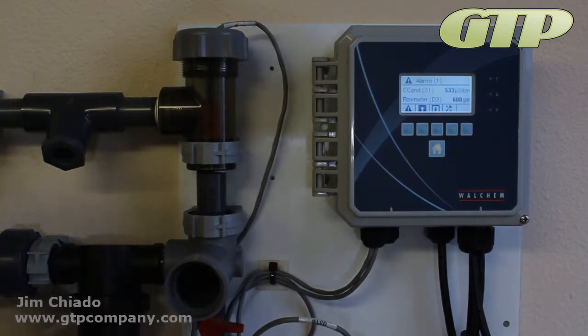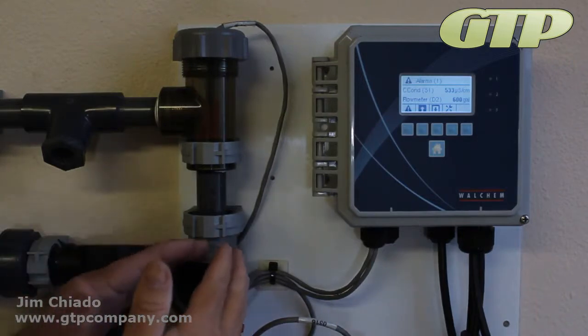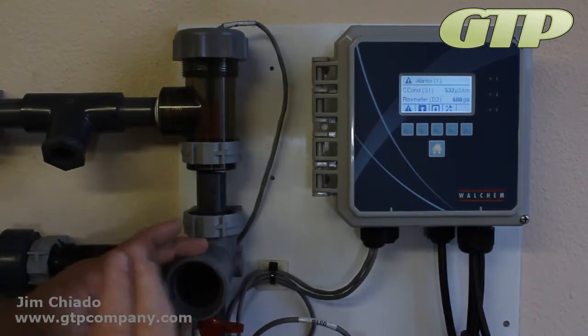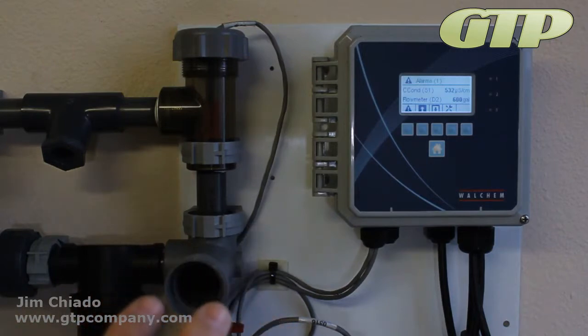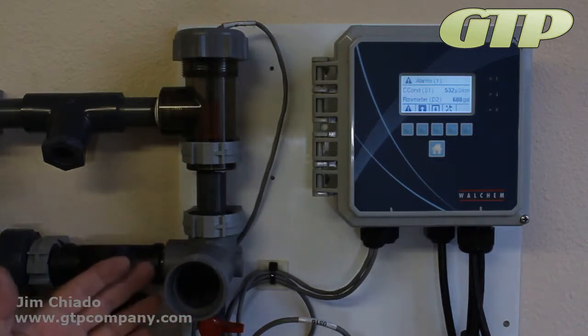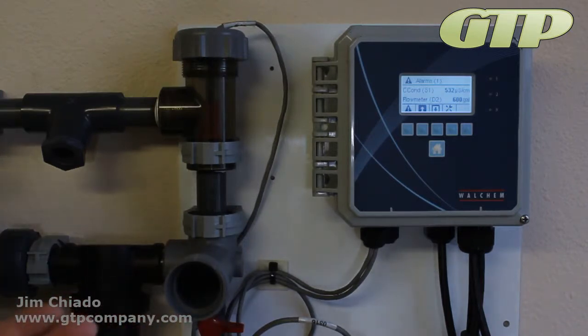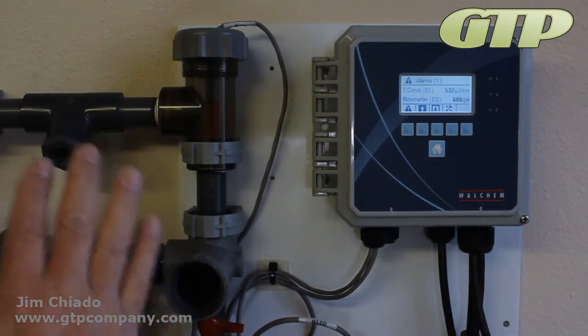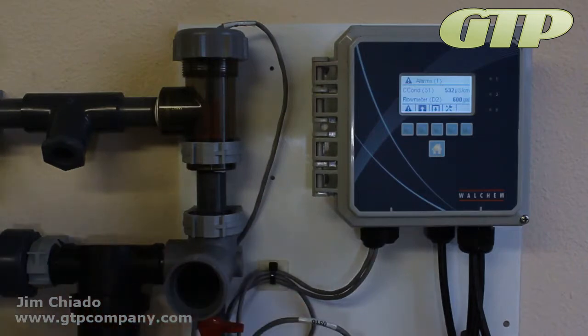Okay, so in the case of conductivity, a lot of people in the field will just leave it in here. I don't really want you to leave it in here, and the reason is that if we don't at least remove this and inspect it, there could be something going on there. Pieces could be stuck in there, paper could be going across the face of it. You could be getting a false reading. So please isolate it, remove it, and put it into here.